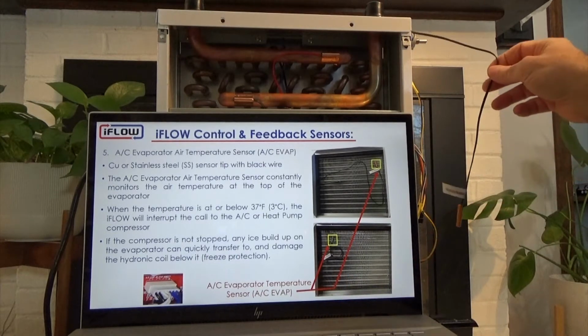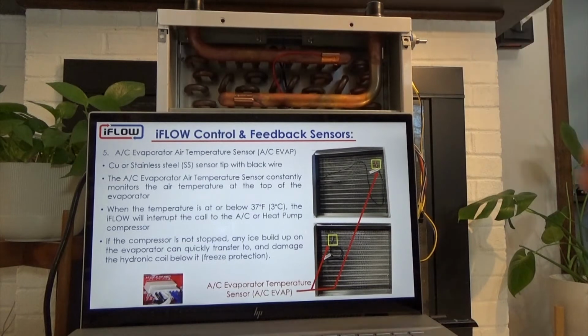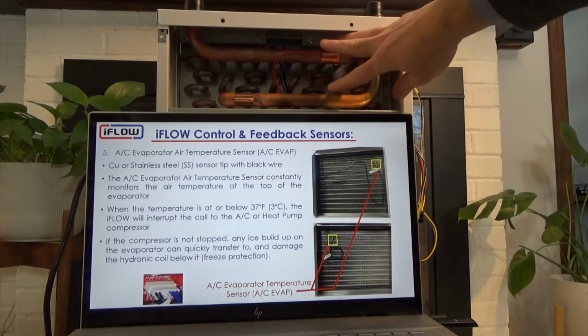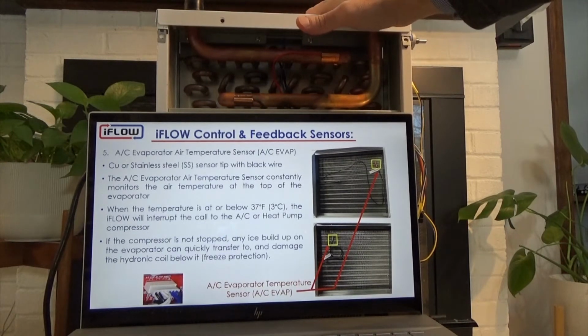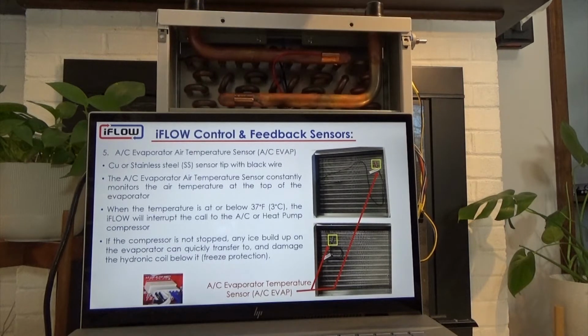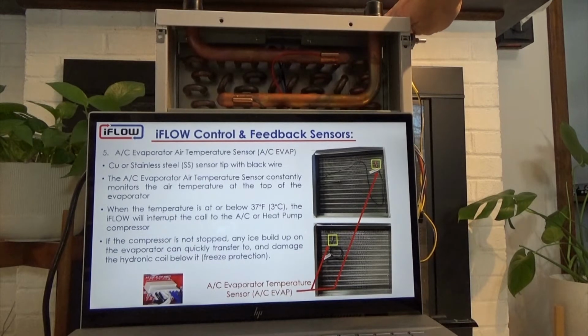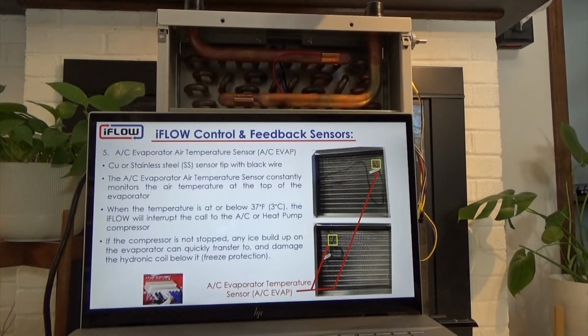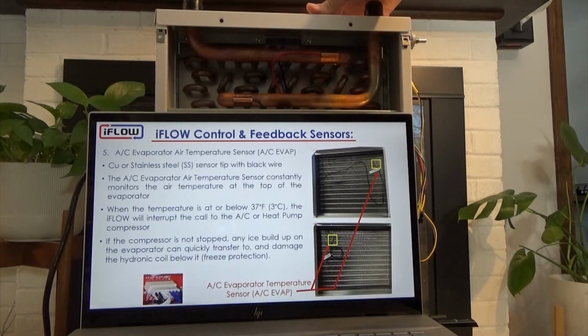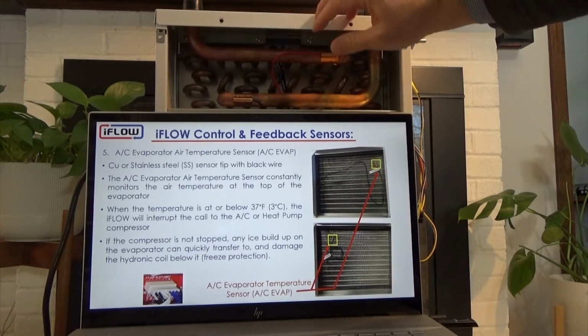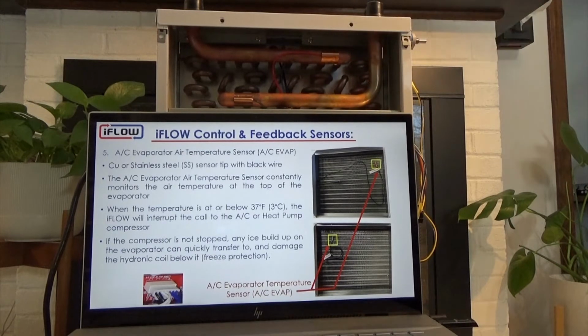That will stop the freezing of the evaporator coil, and it will also provide freeze protection to the hydronic coil, because you can imagine if the AC coil on top is starting to freeze up and that ice is building down towards the bottom of the coil, as the condensate drips down that way, that's getting very close to the hydronic coil. If you have any buildup of ice on the hydronic coil, the transfer is very, very quick, and you can actually damage some of the hydronic coil.